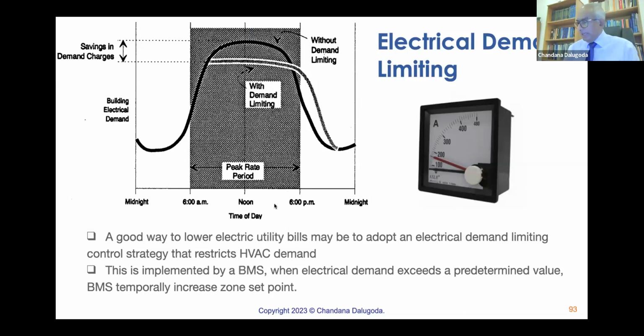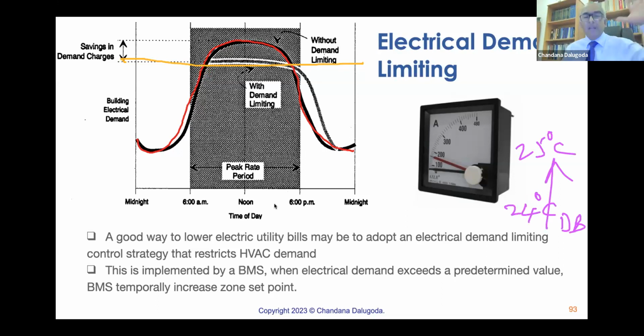What happens? See, our demand is now going up. Can you see? Now you are going up, but our energy cap is here. We can't go above it. When the energy consumption reaches the demand charge value, the BMS sends a signal to all the DDCs to change the AHU set point. What is the set point? Normally 24 degrees C dry bulb, increased to 25 degrees C. What will happen? All the chillers will unload instantly. And this will not shoot up. It will go like this.